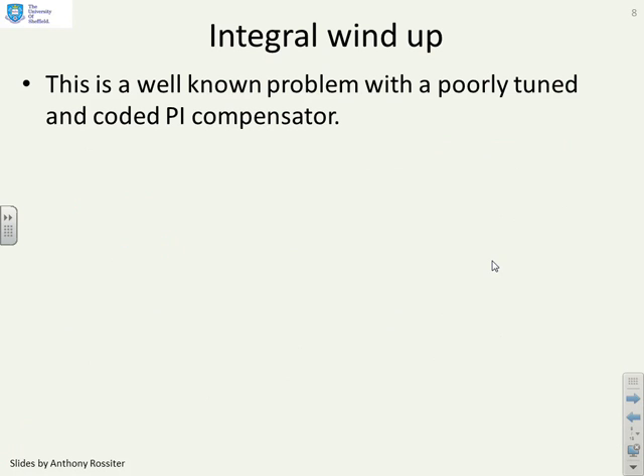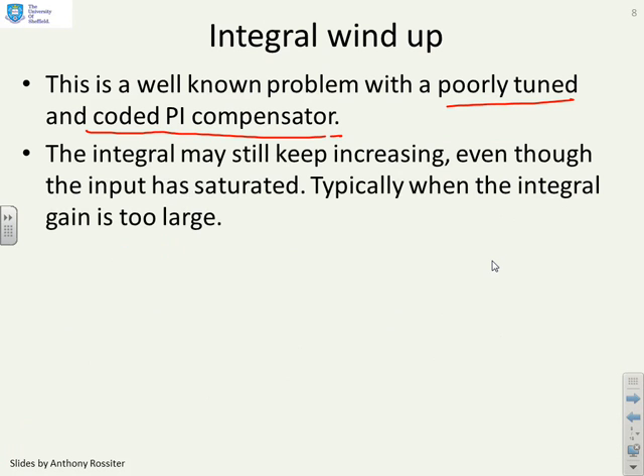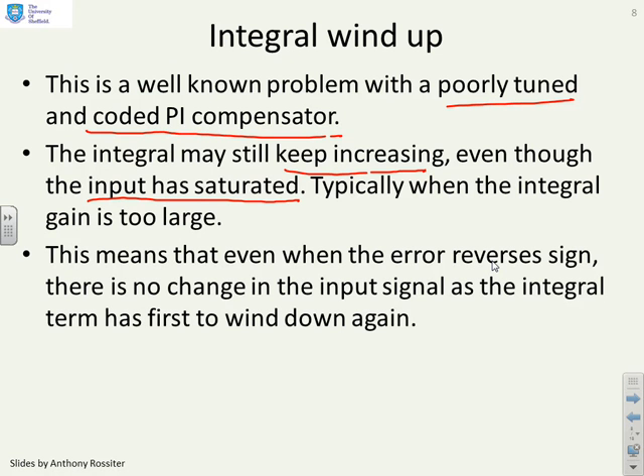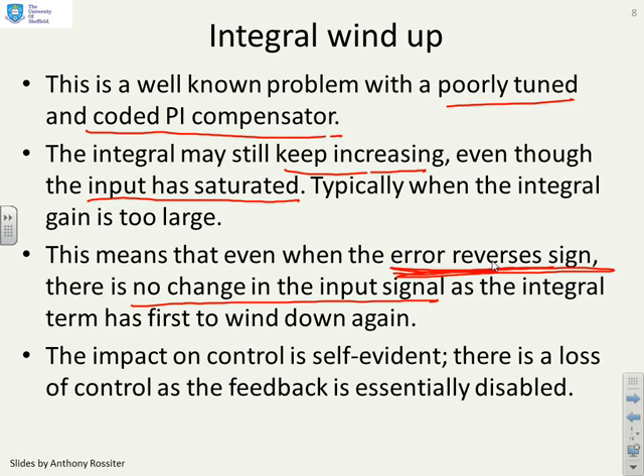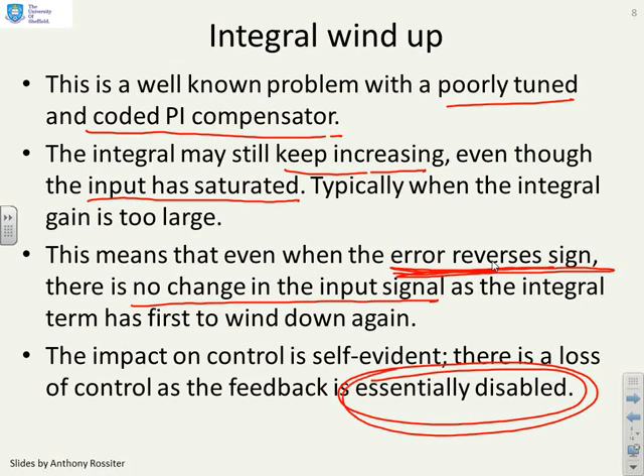Let's look at this concept of integral wind-up. It's a well-known problem with a poorly tuned and poorly coded PI compensator. In simple terms, the integral may still keep increasing even though the input has saturated and you can't actually increase the input anymore. Typically this might happen when the integral gain is too large. The problem with this is that when the error reverses sign and you expect the input to change direction, actually in the first instance you will see no change in the input signal at all because the integral term has got so large that it has to first wind down again before you can change sign. You'll see that in a minute with the simulations. The impact on control is self-evident. There's a loss of control as the feedback is essentially disabled. Changes in error in your summing junction actually have no impact on the control law because of this integral wind-up.